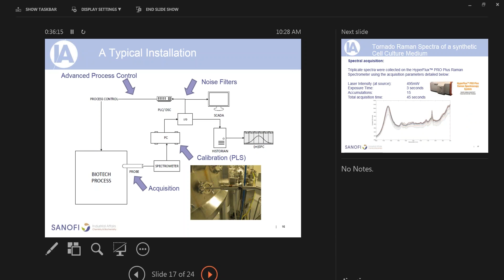This is a Tornado system that we did the study on. Most off-the-shelf Raman spectrometers, to give you some context, take 15 minutes to take a measurement. That's sufficiently sensitive, and even then, it's battling to measure anything better than glucose and lactate reliably. Here, we're using the Hyperflux Pro system. The laser intensity is almost 500 milliwatts at the source. By the time it gets out to the system, it's less than 300 milliwatts. We have an exposure time of 3 seconds. Contrast that even to a 15-minute measurement. And we're taking 15 accumulations, giving us a total acquisition time of 45 seconds.